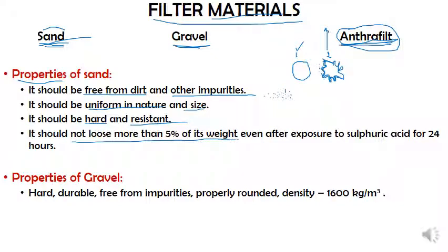And lastly, it should not lose more than 5% of its weight even after exposure to sulfuric acid for 24 hours. So even after 24 hours of exposure to sulfuric acid, the sand should not lose more than 5% of its weight. If the sand complies with all the conditions we have discussed, then that sand can be used as a filtering material. Now similarly, properties of gravel.